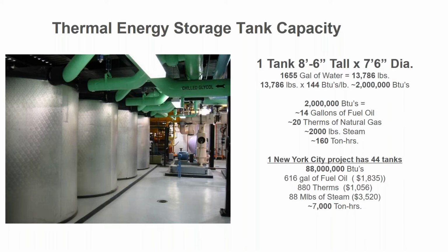If you look at the pounds of water associated with them, it's essentially in each one of these tanks that are 7.5 feet in diameter, 8.5 feet tall, you've got 2 million BTUs of energy, right? Now that's equivalent to 14 gallons of fuel oil, about 20 therms of natural gas, about 2,000 pounds of steam, or 160 ton hours of cooling, if you want to look at it that way. And so we have different projects in the city, and you can look at these tanks and how much value is associated with the energy in them if you consider the regular price of fuel oil or therms or steam. So it's not an insignificant amount of energy that's in these tanks.